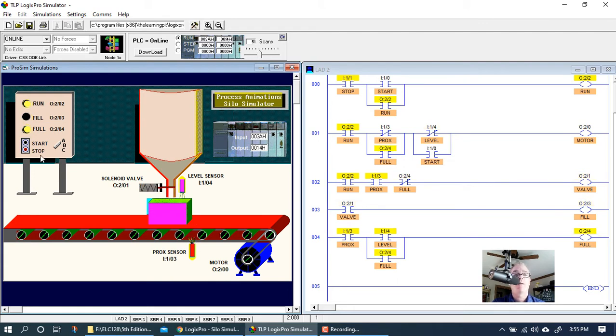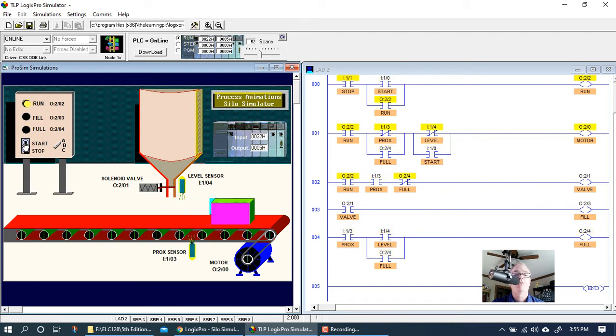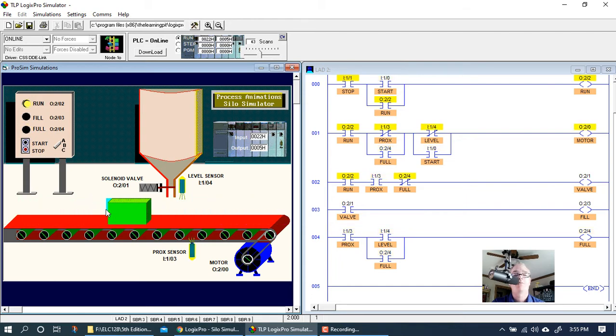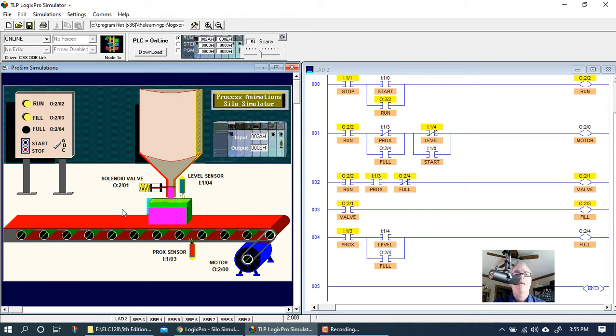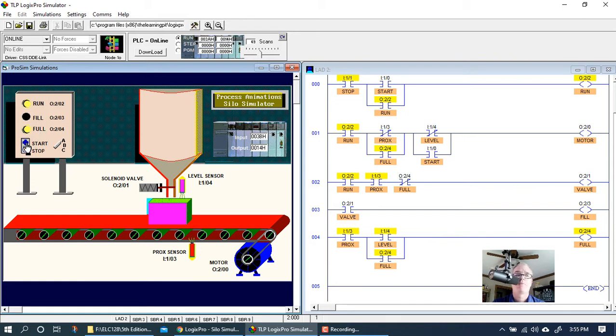Momentarily pressing the start just kind of bumps the box over. It's just bumping the conveyor until the box gets past the proximity sensor. So this is what they were telling us. To get this to work properly, I've got to hold the start button down until the box gets past the proximity sensor. Then it appears to work great. But you can't hold the start button down.